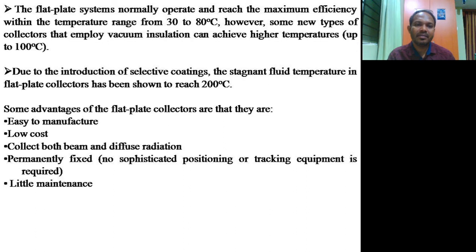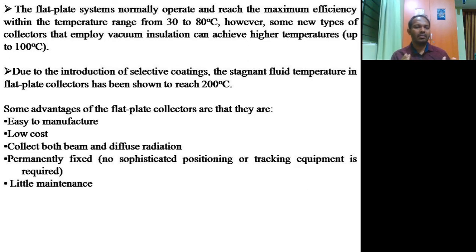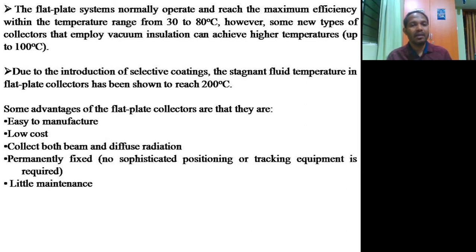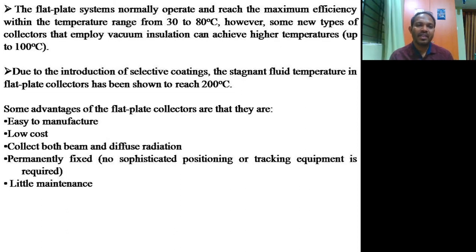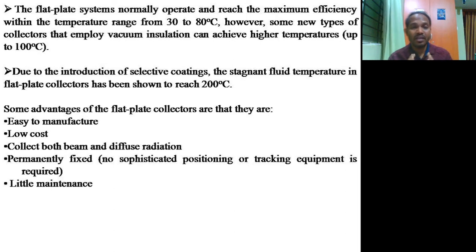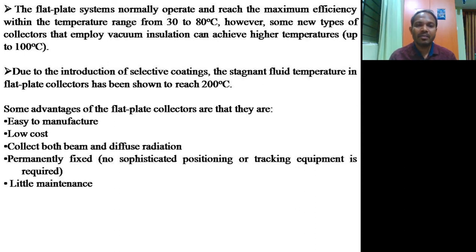Flat plate systems normally operate and reach maximum efficiency within the temperature range of 30 to 80 degrees centigrade. The water can reach up to 80 degrees centigrade — it does not reach 100 degrees, which is good, as a phase change would damage the system. For domestic applications, 45 to 60 or 50 degrees centigrade is more than sufficient, and we place flat plate collectors based on the capacity required.